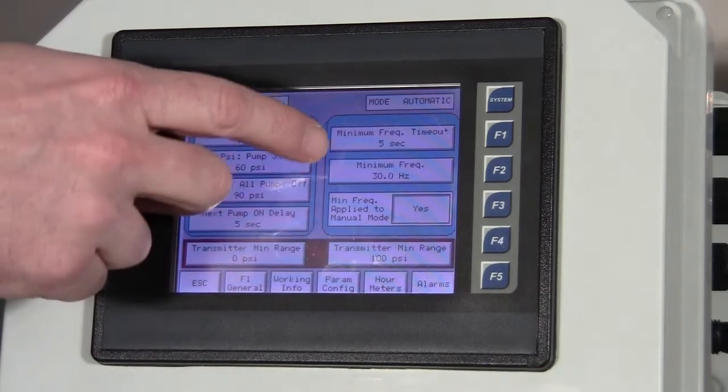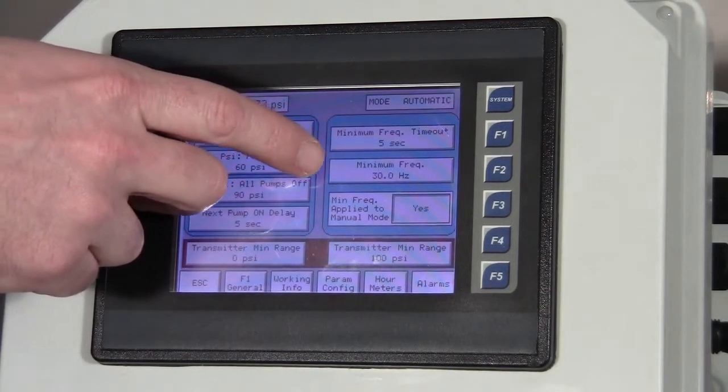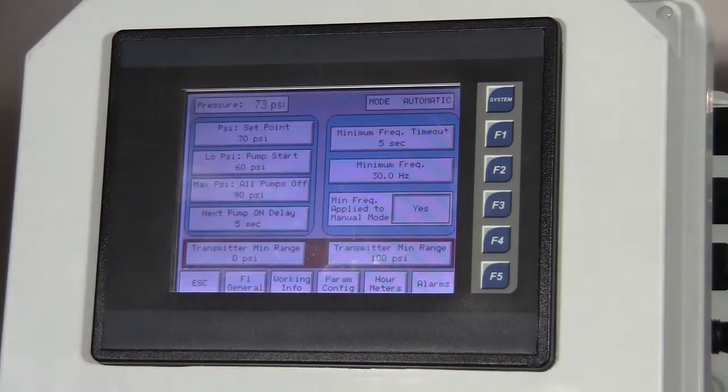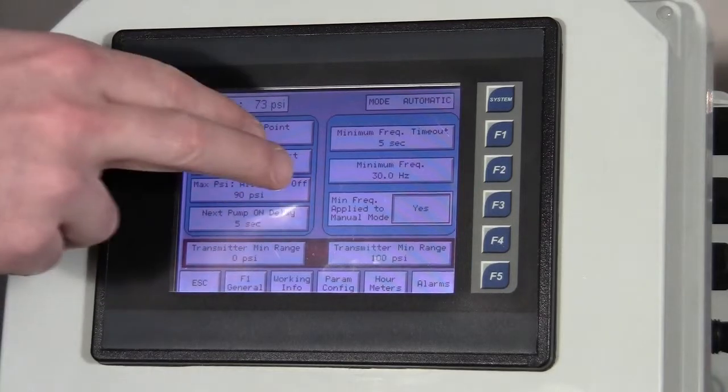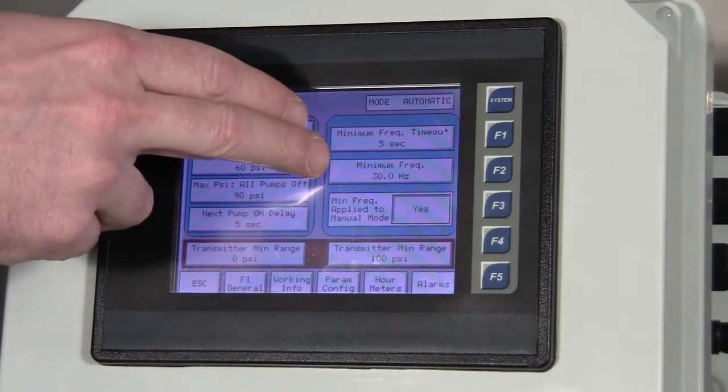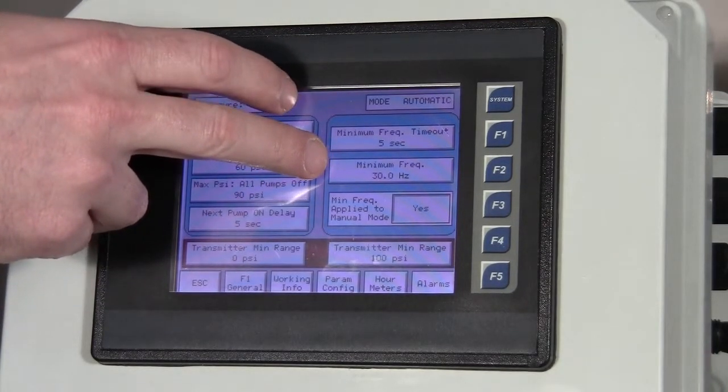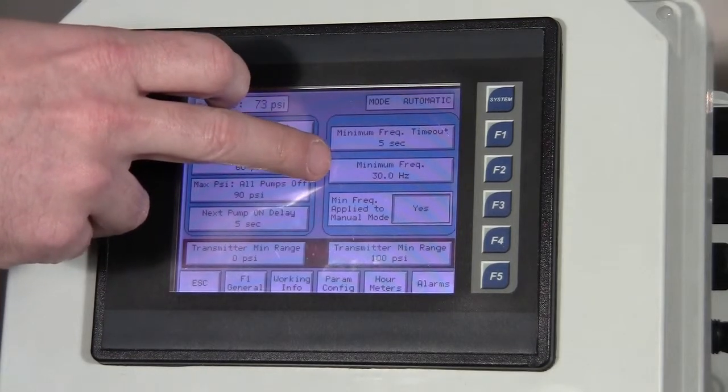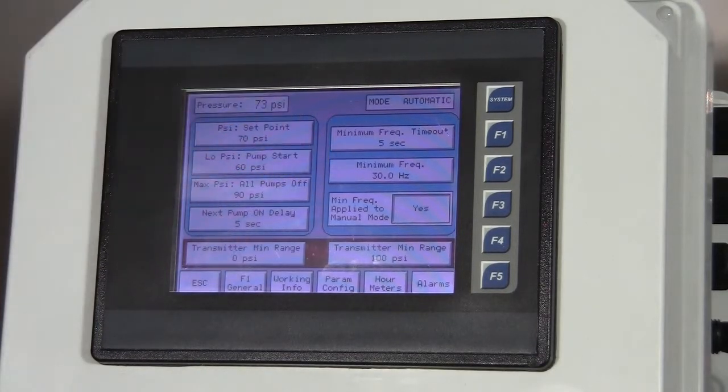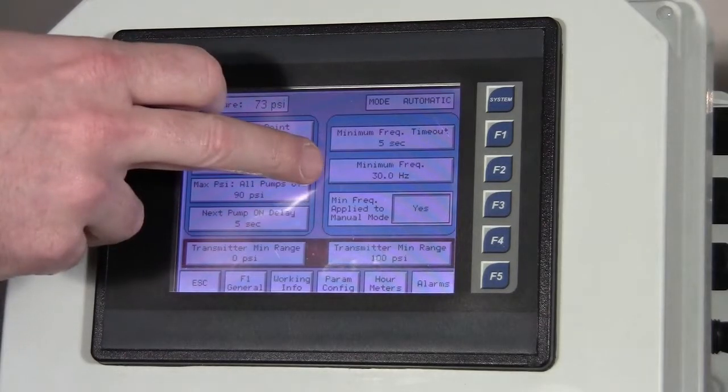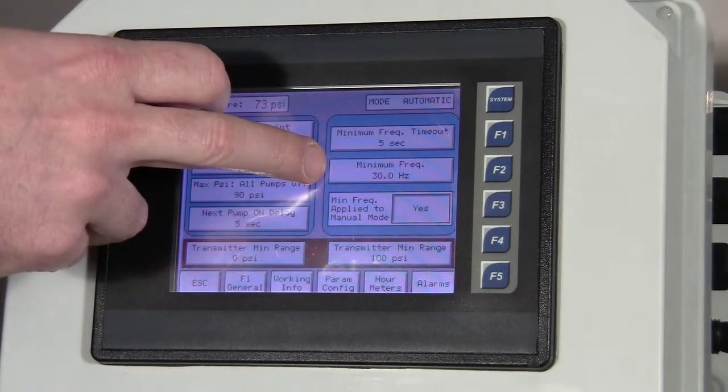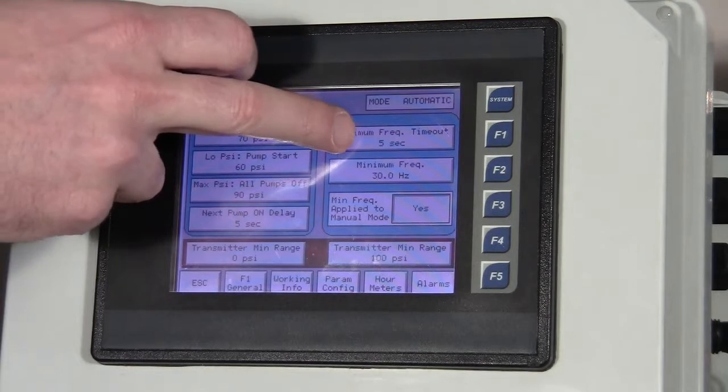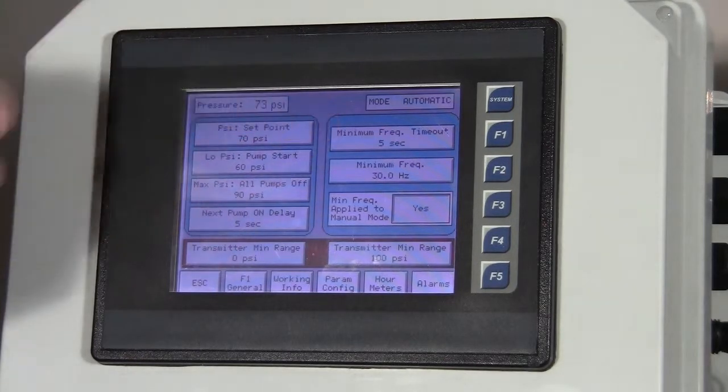Now, over on the right side, we have the minimum frequency and the minimum frequency timeout. The minimum frequency is just that. We don't want the drives to run lower than what we have set here. Right now I have the minimum frequency set at 30 hertz. So if a drive runs at 30 hertz for five seconds, which is what I have set here, then it shuts off.